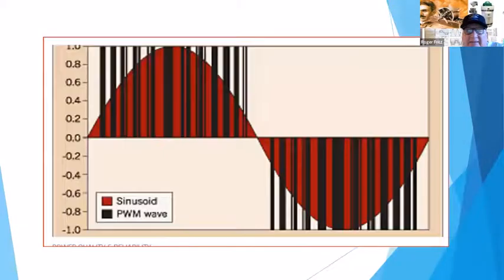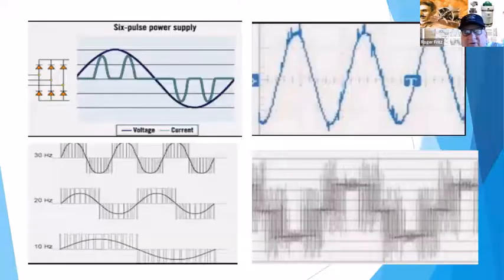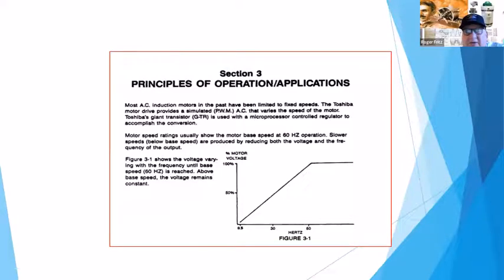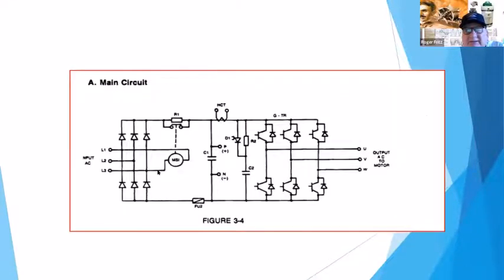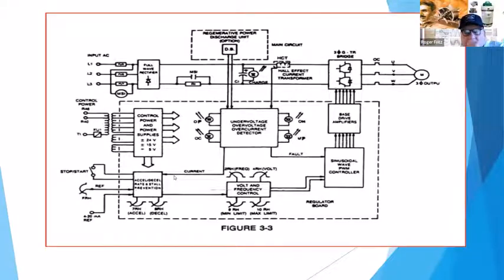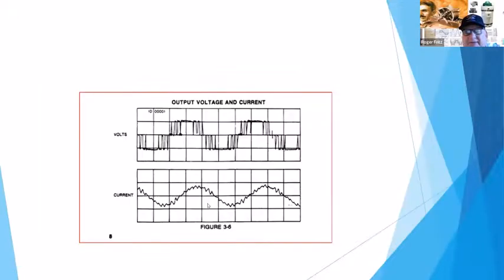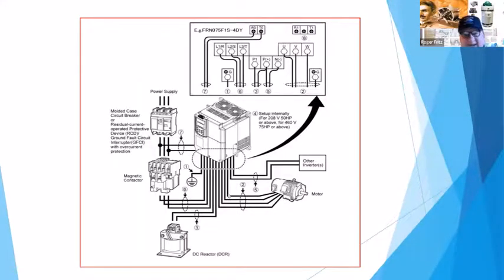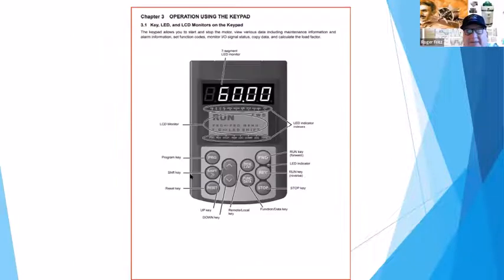Again, the simple main component parts of the drive, I went through those. But then, a lot of people just need to look at their application and what they want to control, and then come back and understand the terminology in the VFDs to make it a very simple solution. It makes it much easier down the road. Otherwise, I see things way over engineered, way over complex. And then when somebody's trying to troubleshoot something, they can't easily find the cause of it. And so they're scratching their head and doing replacement of products to determine what the fault was. Well, that's not the easy way to do it.